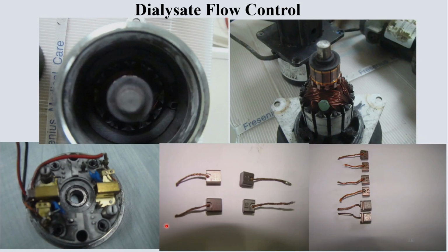Also, over a period of time, these carbon brushes will be shaved down and will not make proper contact with the rotor, which leads to sparking, one. And secondly, a point of time comes when it is not delivering the necessary current to the rotor of the motor. At this point, the carbon brushes have to be changed.